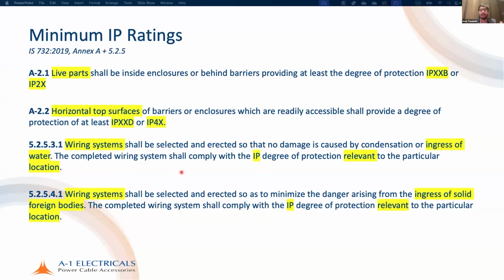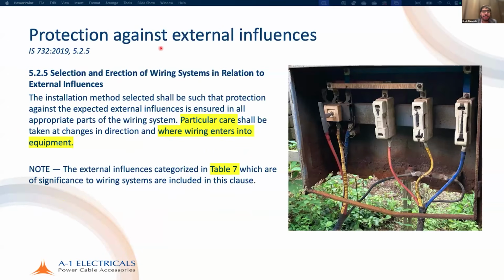However, in most cases, particularly in India, we have a lot of dust and a lot of water. So these two requirements are relevant to the type of external influences. Now, what is protection against external influences? See, the installation method selected shall be such that protection against the expected external influences is ensured in all appropriate parts. So it doesn't just apply where the cables are and where the cables enter the enclosure. Anytime you have any conductors or support, any part of the wiring system, it is required. Particular care should be taken where there is a change in direction and where wiring enters an equipment.